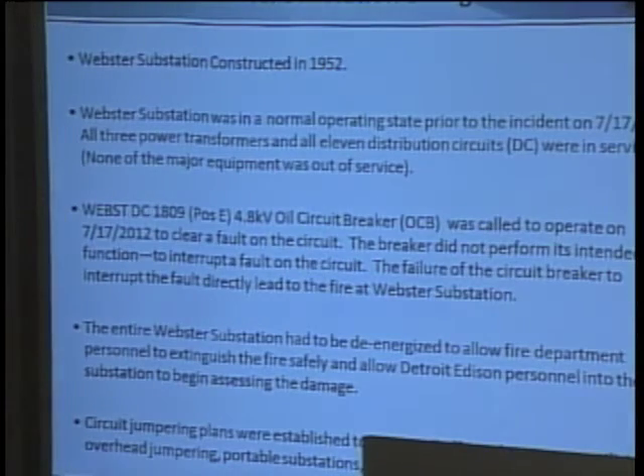The entire Webster substation had to be de-energized in order to allow the fire department to put out the fire. And during that time period, I have a couple of pictures at the end which would show why the substation had to be shut down. And due to the pollution and everything, the ash and the soot, we had to have the substation shut down for a period of time while they cleaned all the equipment inside the substation.